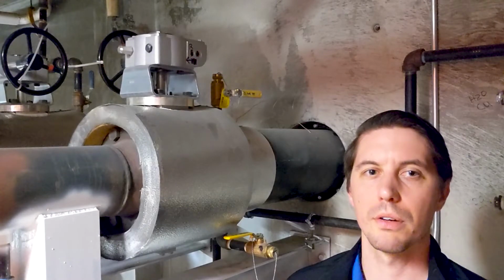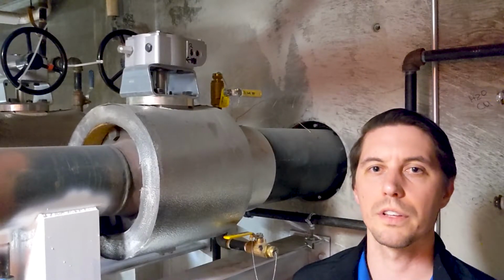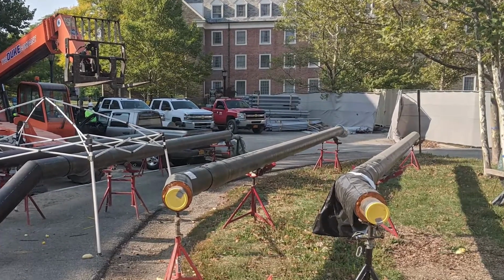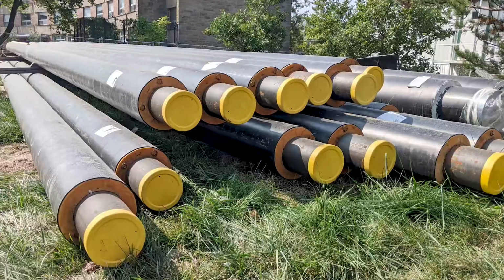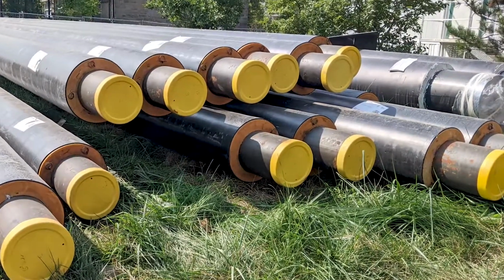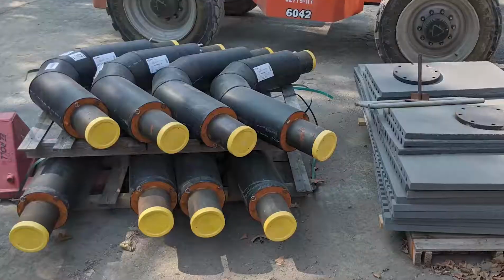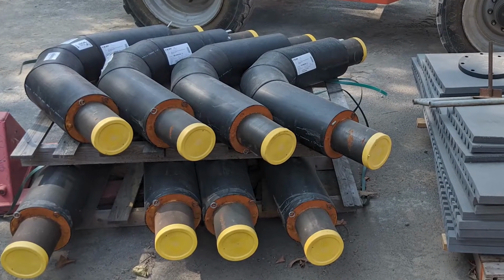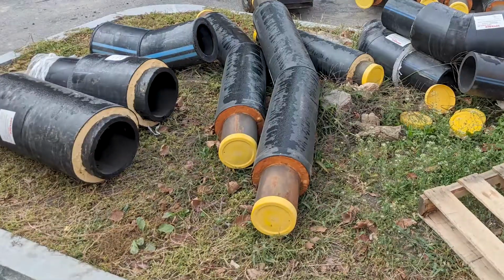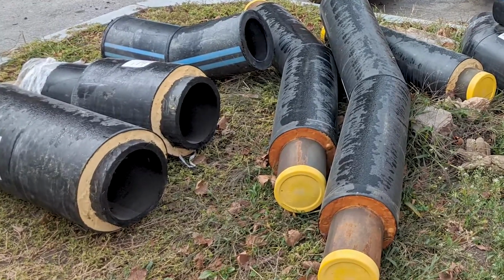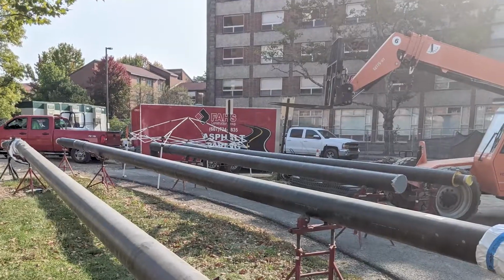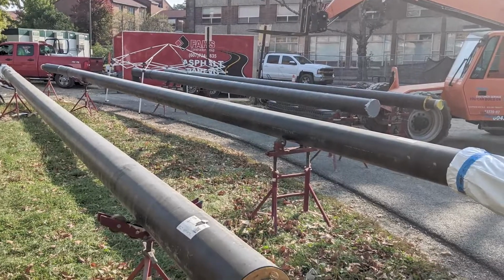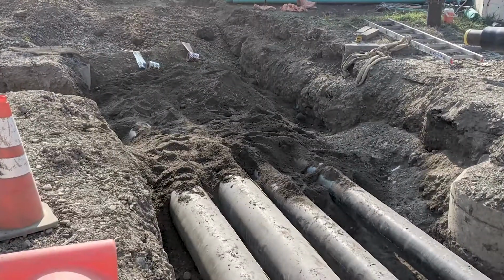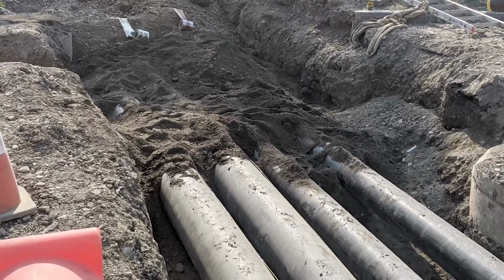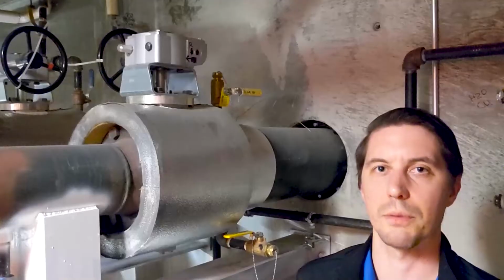Distribution piping to the buildings is constructed of EN 253 thin wall steel that is insulated in foam and protected with an HDPE jacket. Thin wall piping is ideal for hot water. It doesn't require a deep burial depth, doesn't require a slope, and doesn't require vaults or manholes. It doesn't need traditional expansion joints either. The shutoff valves are insulated and directly buried. This is a very cost-effective product for running long distances on campuses.